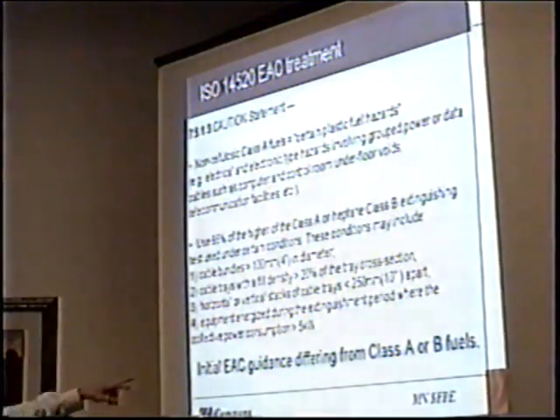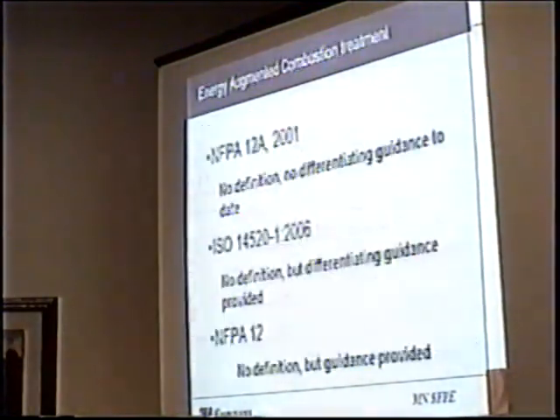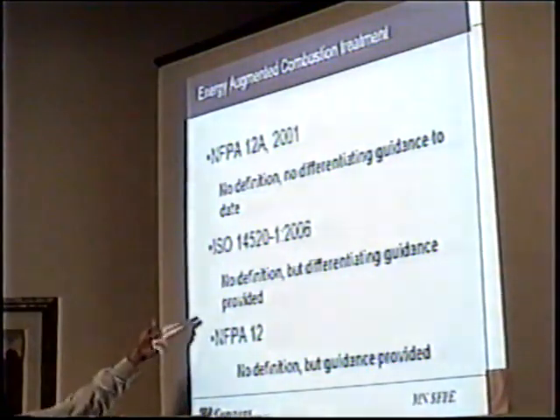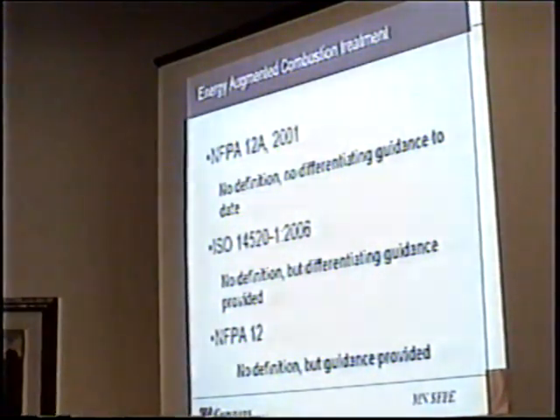Now, this is initial guidance differing from Class A or B fuels. Is it right? We don't know. That's half the problem. So, just to recap, NFPA 12A: no definition of what a Class C fire event or energy augmented combustion is, no differentiating guidance. ISO 14520: no definition, but you do have differentiating guidance provided. NFPA 12: no definition, but there is some guidance provided.